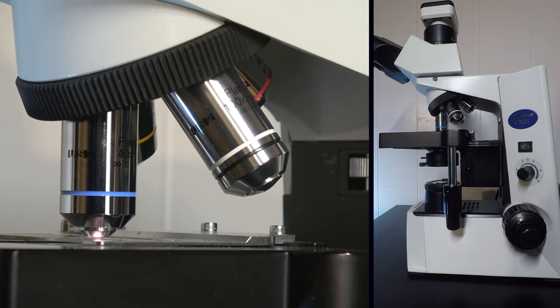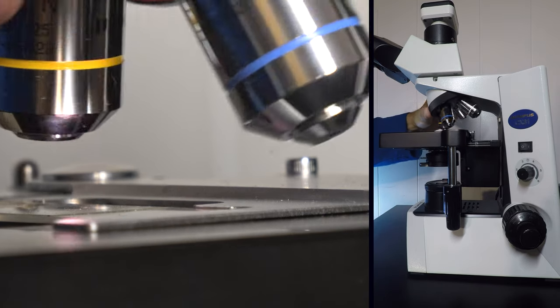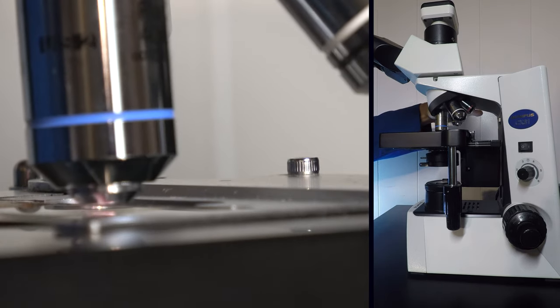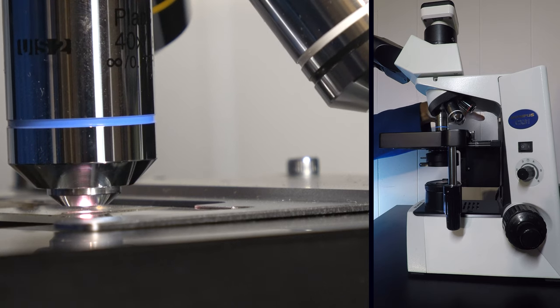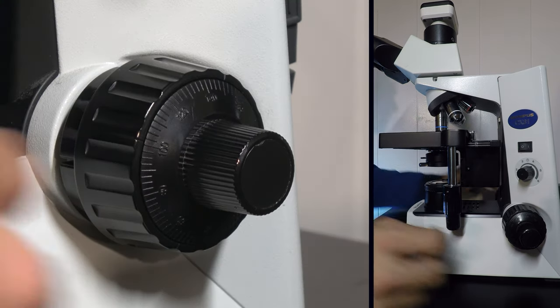When using these higher powered lenses, you want to carefully rotate them into place. The slide and lens should not make contact. The distance between the slide and the lens is called the working distance and will decrease as you increase objective size.